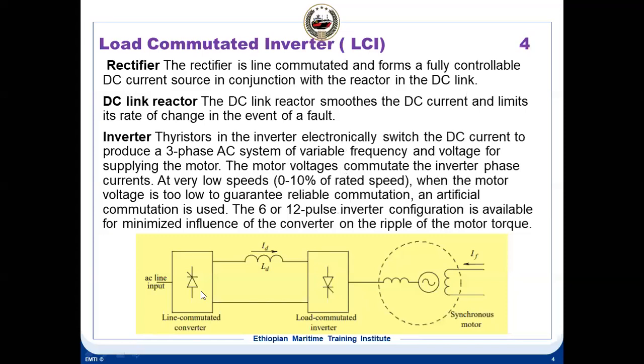The rectifier is line commutated and forms a fully controllable DC source in conjunction with the reactor in the DC link. The DC link reactor will smoothen the DC which is coming here. It will filter it out and limit the rate of change of current in the event of a fault. Then you have the thyristors. The thyristors in the inverter electronically switch the DC current to produce a three-phase AC output of variable frequency and voltage for supplying the motor. The motor voltage commutates the inverter phase currents.